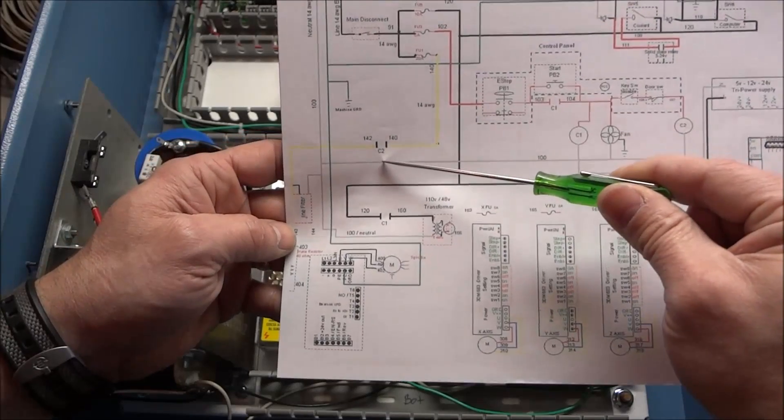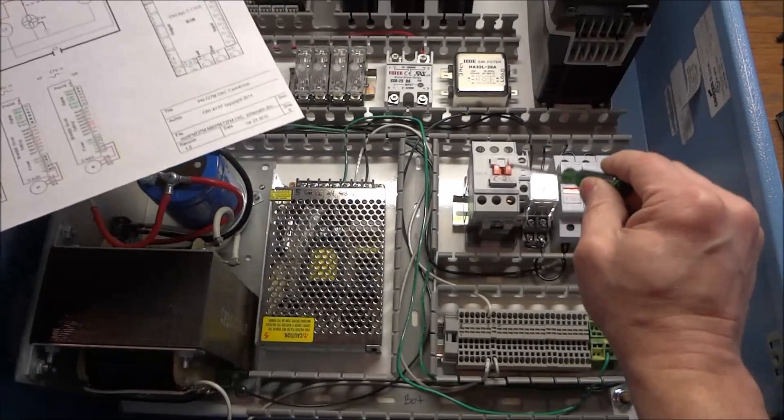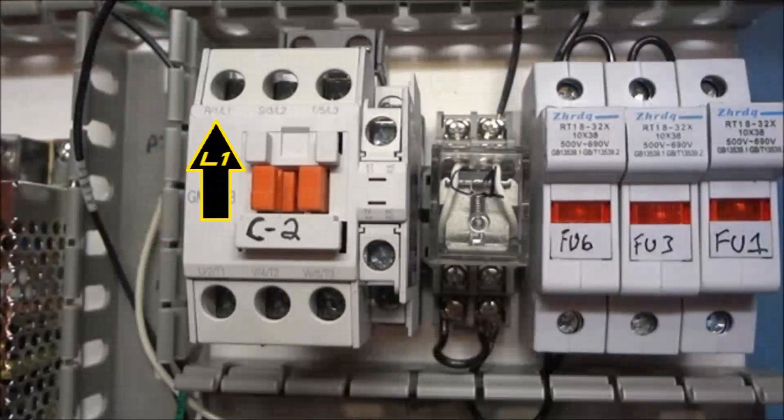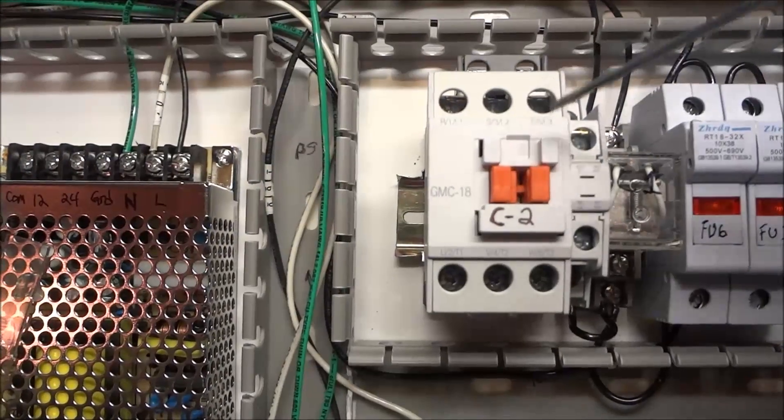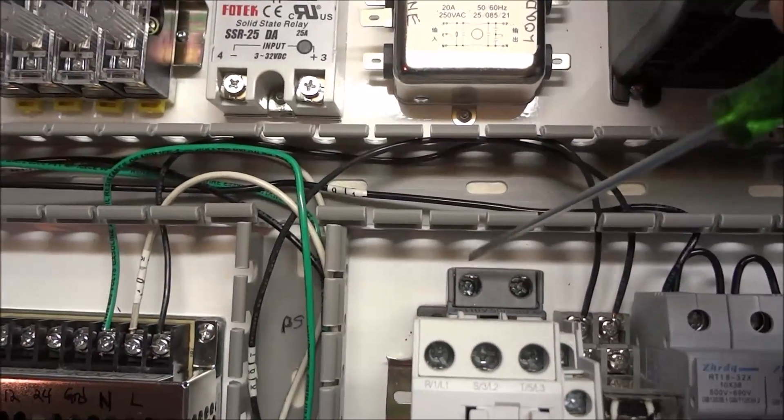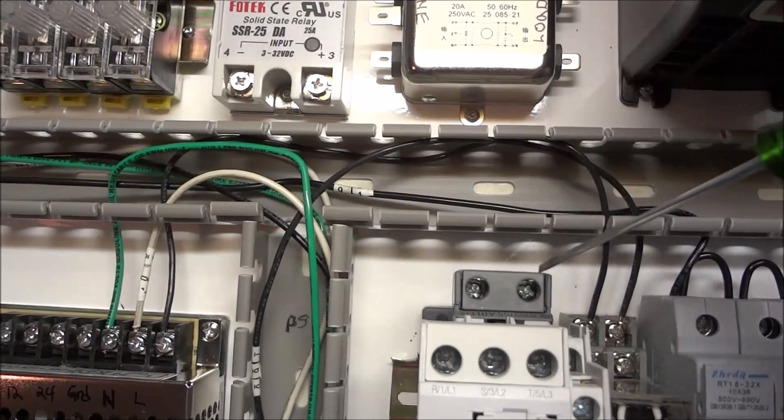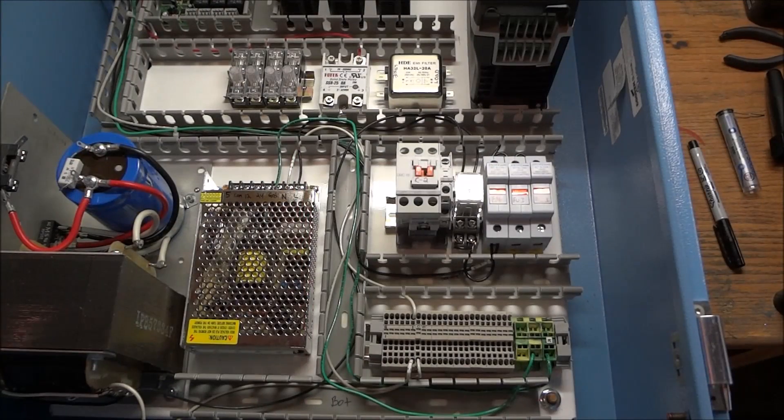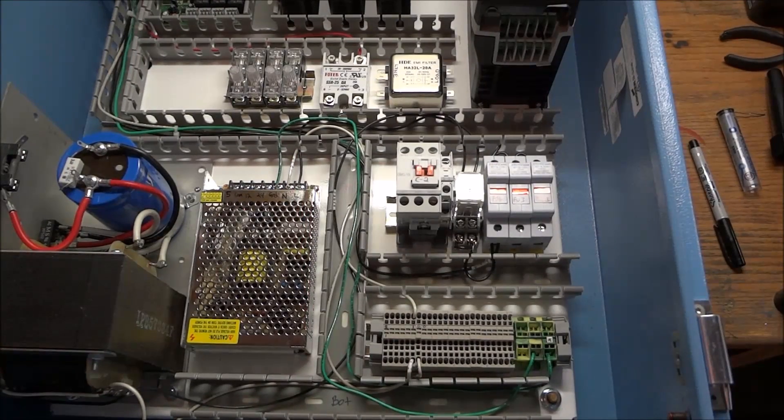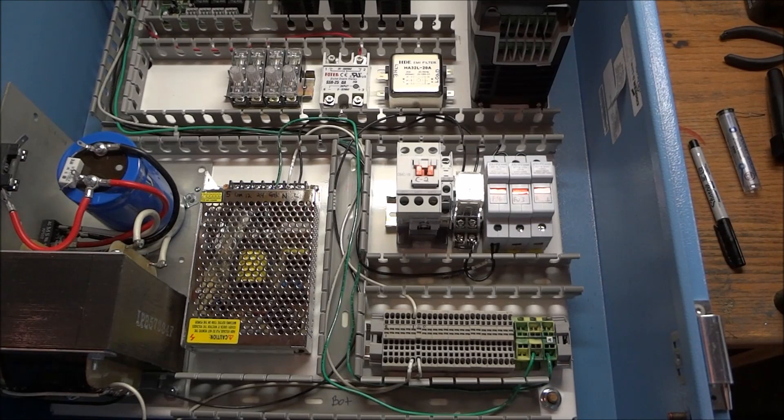Now this is the C2 contactor, the big contactor. And we're going to bring power in L1 and out through L2. We have three sets of contacts here. And over here, these gray connectors, that is our power to our coil for C2. So we want to come out of our fuse 1 using 14 gauge here.